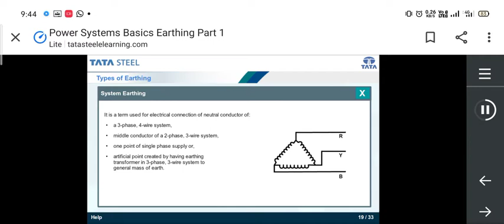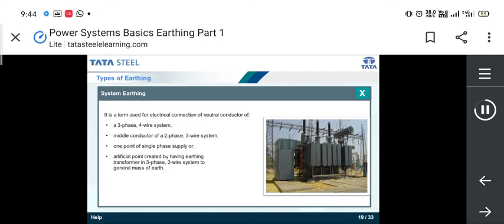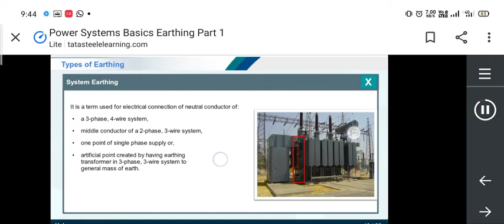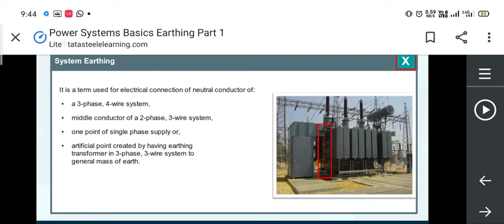System earthing. It is a term used for electrical connection of neutral conductor of a three-phase 4-wire system, middle conductor of a two-phase 3-wire system, one point of single-phase supply, or artificial point created by having earthing transformer in three-phase 3-wire system to general mass of Earth. As you can see, this image shows a star-delta transformer wherein the neutral point is earthed. The highlighted area indicates the neutral point that has been earthed. This is an example of system earthing.